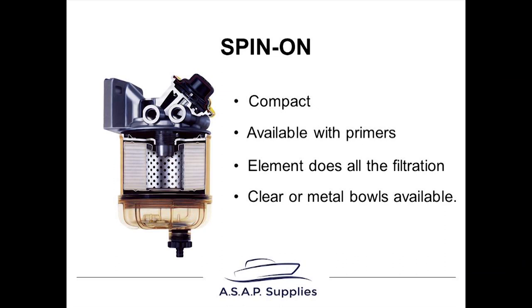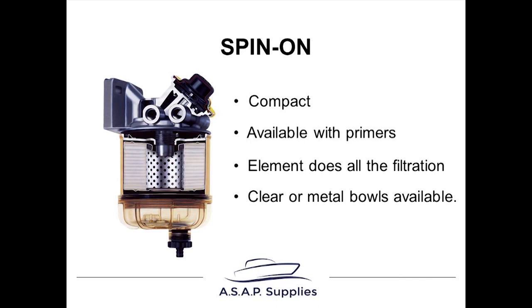Then you get onto things like the Racor spin-on filters. Racor elements are treated with what they call Aquabloc - a treatment process designed to prevent any water from going through. The water beads up on the surface of the element and coalesces, basically like condensation on a window - the little particles join together, form a bigger particle, eventually become heavier than the diesel, and then fall to the bottom. That particular one has a primer.